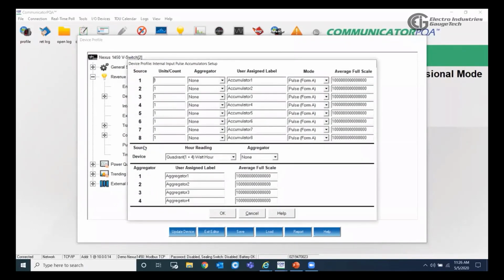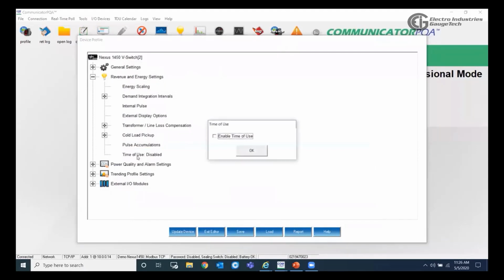And then we have the pulse accumulation, where we can set the 8 pulses and all the aggregators for the meter. And the last one is the time of use, where we can enable it from here. Of course, like everything we are doing here on the profile, we are doing on the software. So at the end of changing everything here, we have to hit update device.